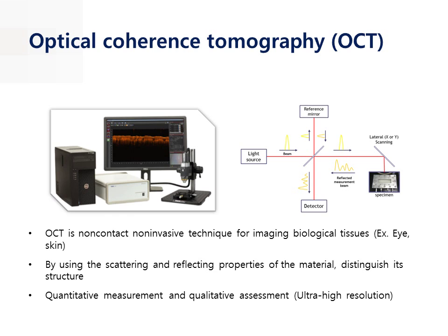The light in the reference beam is reflected from a reference mirror at a variable distance, which produces a variable time delay. It is combined and detected with the light from the specimen, which has multiple echoes, and the light from the reference mirror, which has a single echo at a known delay. Then, by comparing those two kinds of echoes, the structure of the specimen is determined.